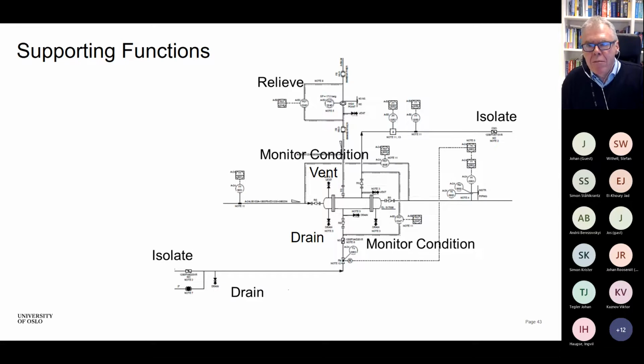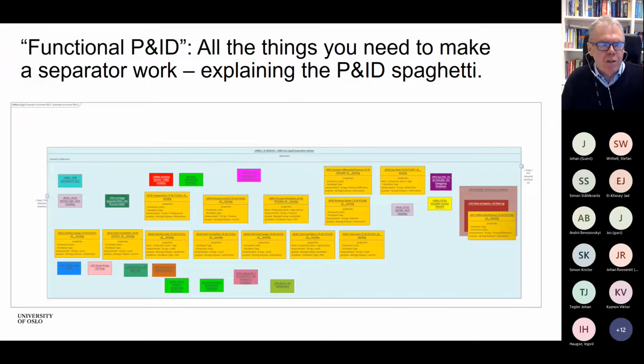This way of modelling has enabled us to create something we call a functional P&ID, where we say that a separation system is not a big separator. It is just a separator with all these 25, 26 additional things you need to do to it and with it. A lot of them about monitoring and sensing, but other things like jetting to make sure it doesn't clog up with sand, or putting a manhole on it so you can do maintenance. Each of these things is capable of explaining why you have a specific piece of equipment or assembly on your actual P&ID.